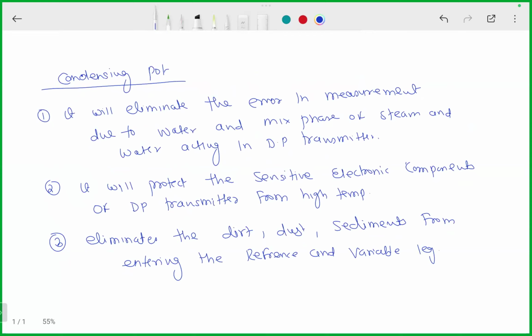If you look exactly at the DP transmitter, at the inlet to the DP transmitter, the density is going to be almost the same. But that is not the concept. The concept is if you are trying to measure one side vapor and other side liquid, your measurements are never going to be correct. So whatever errors are going to occur due to this different phase, that is eliminated with the help of your condensing pot.